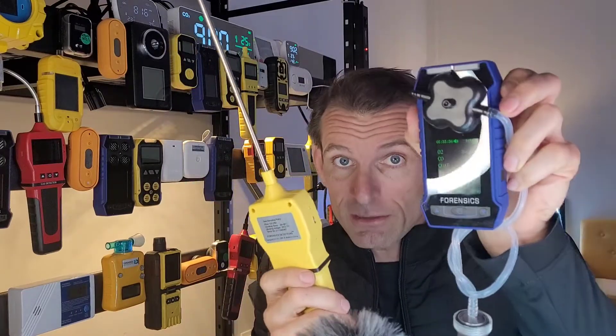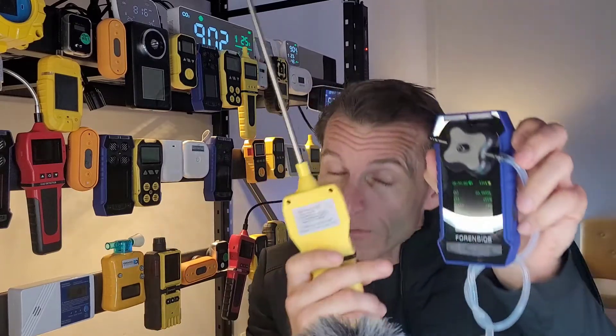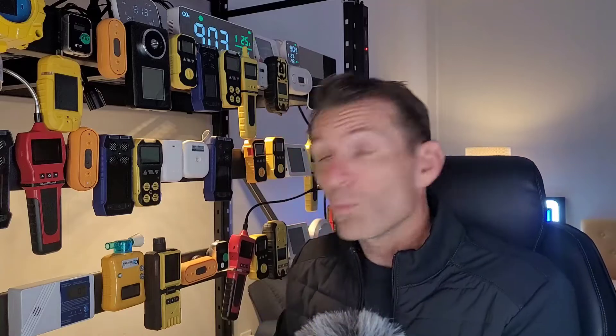It's analyzed by the gas analyzer. Carbon monoxide range: zero to one thousand ppm. Oxygen range: zero to thirty percent — though you don't need the full thirty percent because in combustion you're going down in oxygen. Resolution is 0.1 percent.